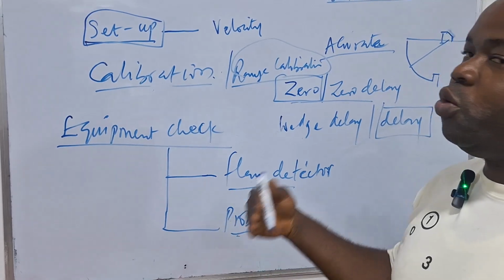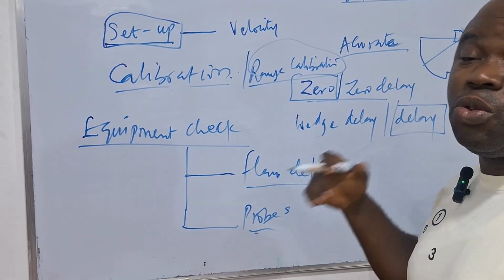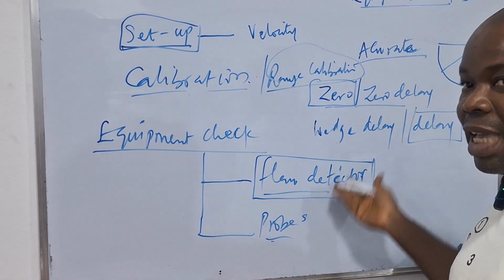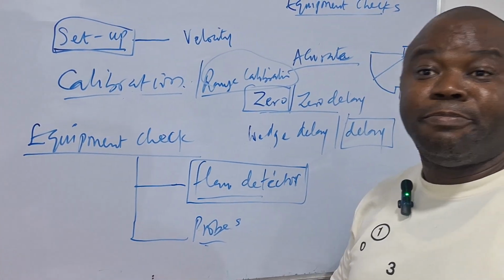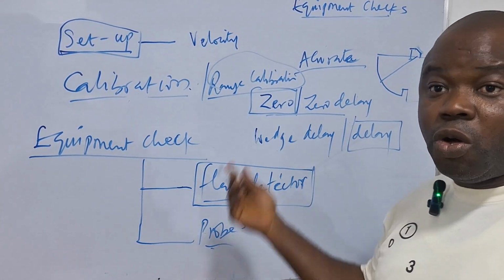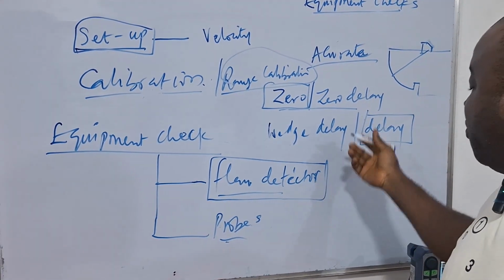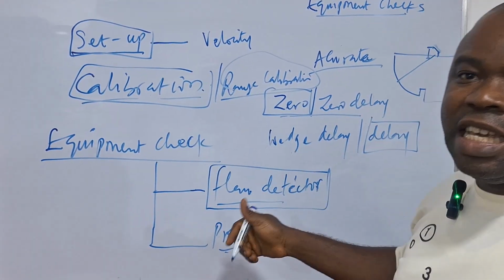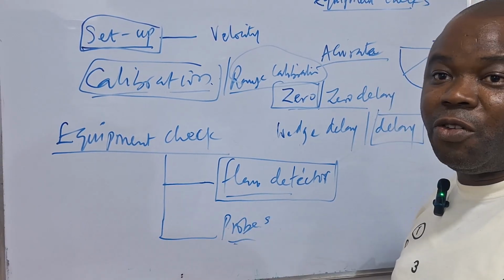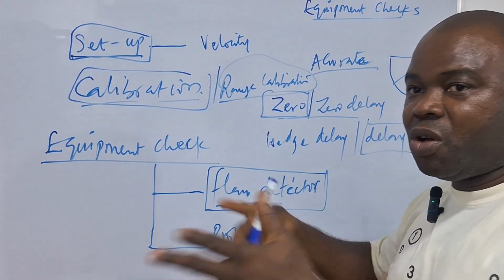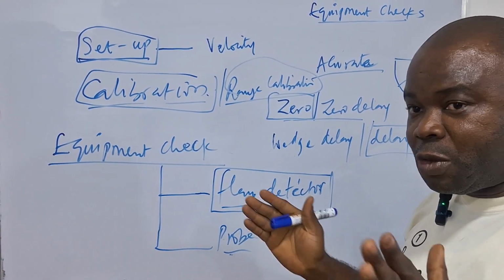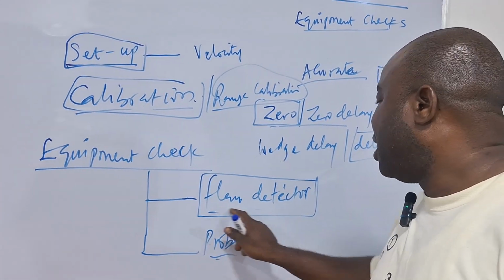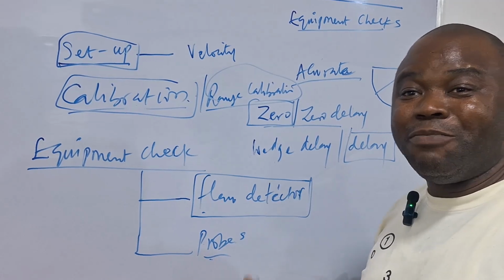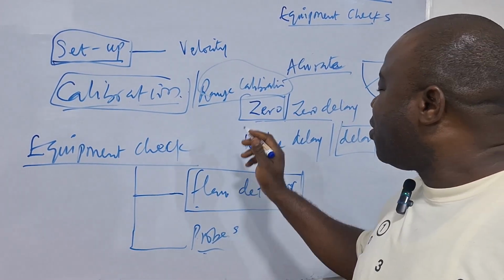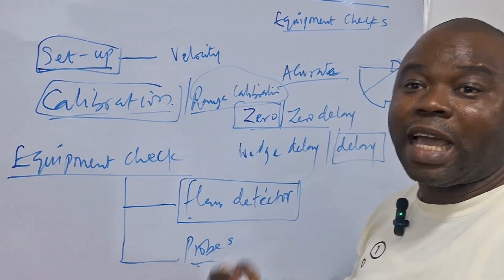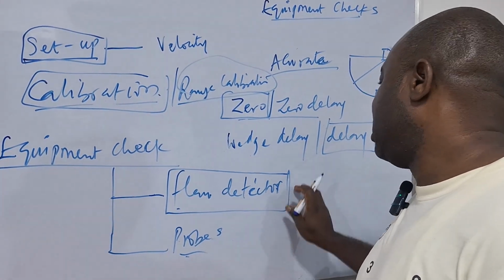Why do you perform this check? It is to see, one, if the flaw detector is giving you an accurate reading. When you perform a flaw detector check and it fails, it means you have to send the equipment back to the manufacturer or to an approved vendor that calibrates for the manufacturer. In this case, the calibration that is done on the machine is quite different from the calibration that you do when you want to test. That is more like a system calibration, where they will use pulse generators and other things to set the equipment so that it comes back to its optimal condition. And basically, as per standard, you are expected to do your equipment calibration every year. So this kind of calibration settles your equipment check, so that by the time you perform your equipment check, you are getting the right result. We are also going to look at those checks subsequently in this video.